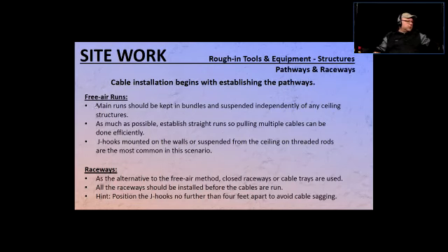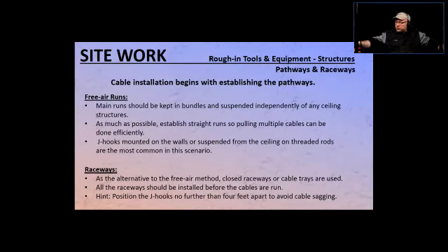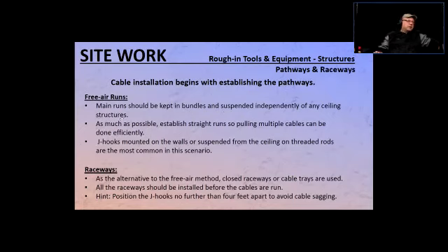We talked about free air runs and raceways. Main runs should be kept in bundles and suspended independently of any ceiling structures — we can't tie anything to anything. Wire runs should be suspended independently, and usually when it comes to data cabling, J-hooks are the order of the day, or cable trays or conduits.